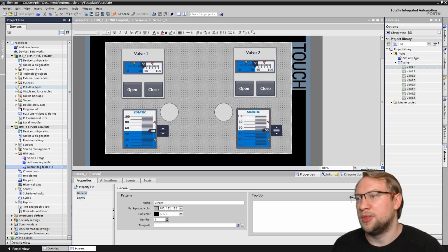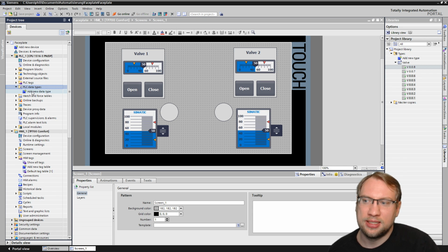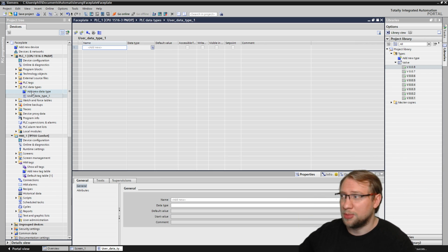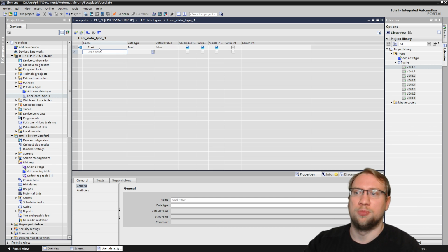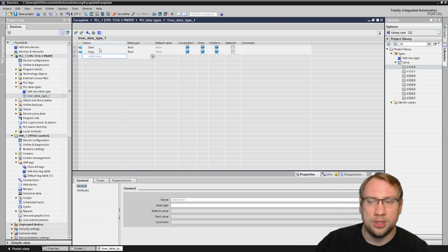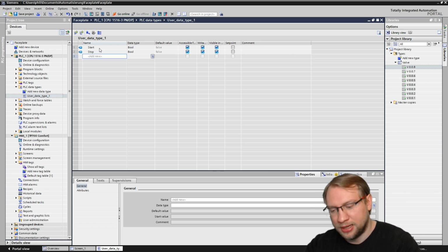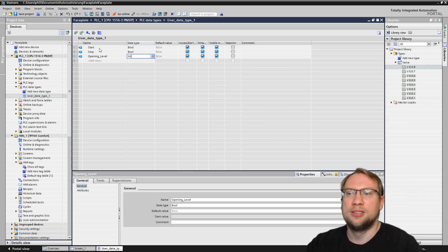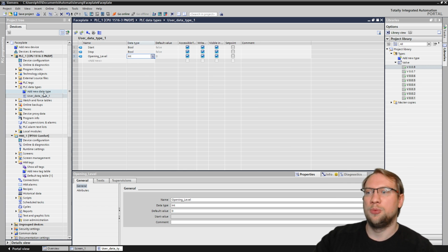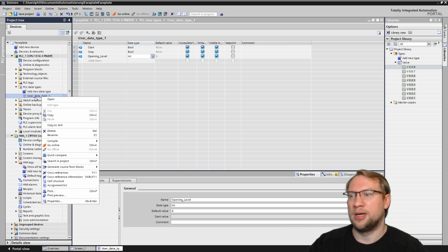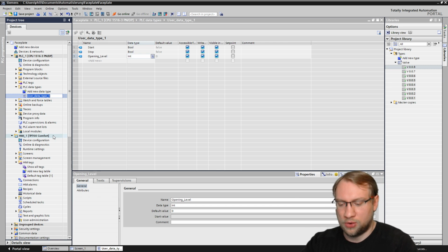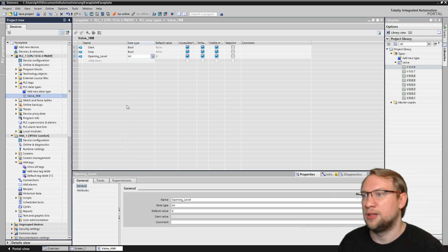So therefore, create a PLC data type. I also made a video about this, so check out my channel. This data type will have a start, which is a Boolean. It will have a stop, which is also a Boolean. And it will have an opening level, which is an integer, actually, not a Boolean. So these three, whenever we use user data type 1 now, these three are in there. So I can also rename this and call it valve HMI, which is the communication to our HMI.